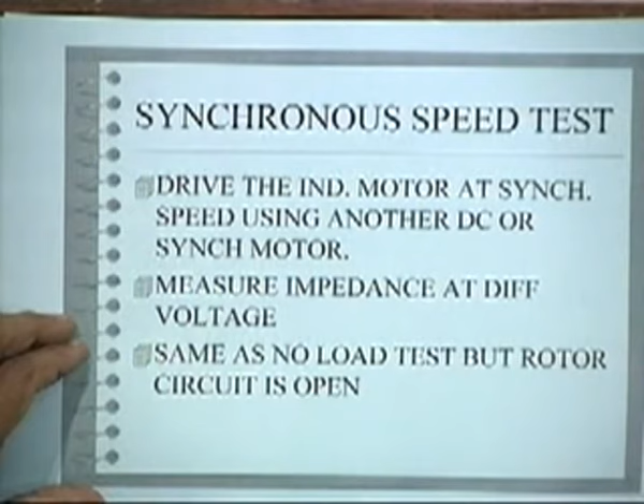Then you measure the impedance at different voltages, as you did in the no load test. You measure the impedance at different voltages, and then it is the same as the no load test, but the rotor circuit is actually open here. So this is one of the tests that are conducted as an accurate method of measuring the core loss. Okay.